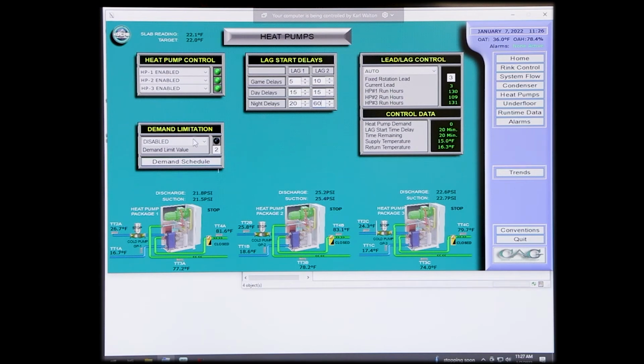Okay? Demand limit schedule. Right now it's disabled. You can, if you choose, enable this demand limit schedule. This schedule is how many compressors you want to run. If you try to go with one, you're going to run one machine all the time. It just won't shut off, unless you really have a high temperature setting. If you're looking for 20 degrees, don't think you're going to get 20 degrees with one compressor.